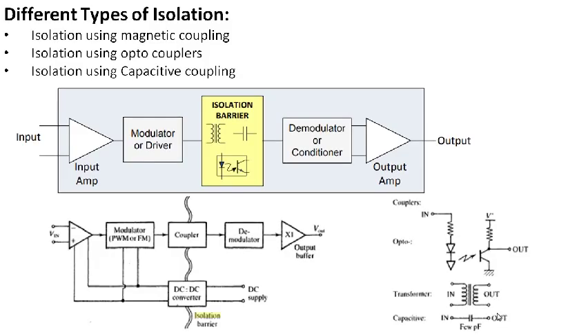There are different ways of achieving isolation: by using magnetic coupling, by using optocouplers, and by using capacitive coupling. In the basic block diagram of an isolation amplifier, the input signal is modulated — converted to a high frequency signal — and sent across the barrier to the measurement circuit side, where a demodulator converts it back to the low frequency signal. Optocouplers are used for optical isolation, transformers for magnetic isolation, and capacitors for capacitive isolation.